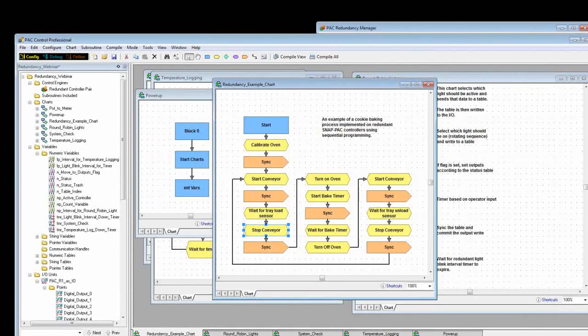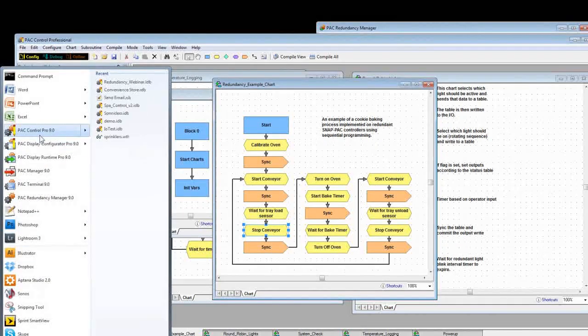Okay, another one. Is the serial connection connected between the two PAC-R ones for the redundancy? I think maybe he means the two PAC S's. Mm-hmm. Because PAC-Rs are not supported for controller-level redundancy. So the serial link between the two PAC S controllers. Is that the question, Alexa? I think. Is the serial connection connected between the two PAC S for the redundancy? No, they're not. The connection between the arbiter and the two controllers are two independent serial links. Right, because the two PAC S's aren't connected serially. They're connected. That's correct. Ethernet crossover. They're only connected Ethernet crossover, right?